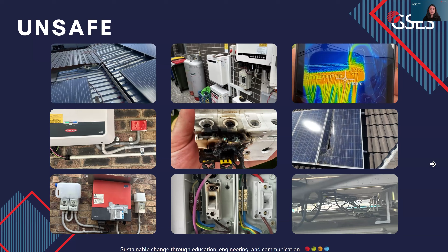The first one, the one that we had the most, I think we had about 25% of this, was loose connections in system cables. Then we had lack of or incorrect earthing for the PV array frame or modules. We have the inverter not installed to manufacturer instructions, so that could mean RSDs were not installed, was a homeowner installation, and so on. Then the AC output of the inverter incorrectly connected to the MEN on the neutral bar. We'll talk about this one in more detail in the case studies.